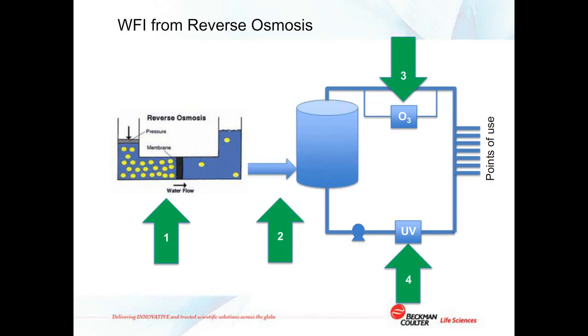Periodically, when the water system is not being used by production, the UV destruct light is turned off, allowing ozonated water to circulate throughout the entire loop. The ozone destroys both microbial contamination and any biofilm that's been built up inside the pipework.